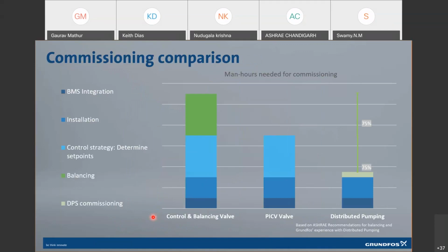But look at it now. You see a huge savings in terms of the man hours needed for commissioning. Now, you do not need a complex BMS integration because here you have an individual pump which has a proper communication channel and gives localized information to your BMS. So you have much more information available, and it is seamless because the moment you know the communication protocol and you connect the system, you have the entire data available.